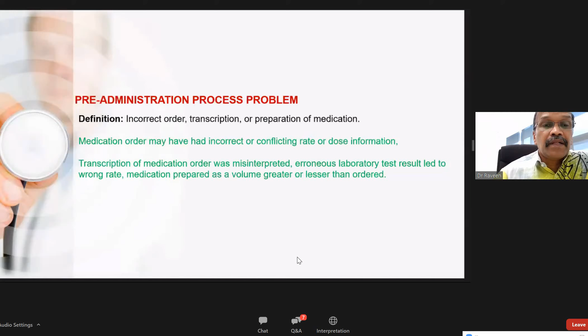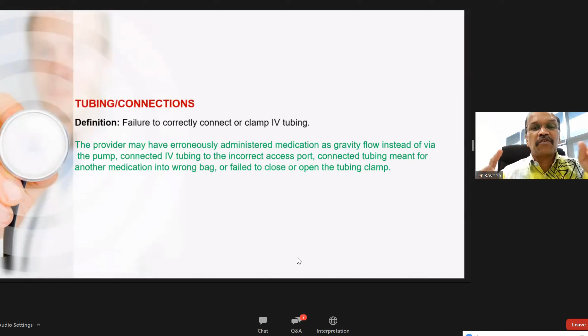Now, failure to correctly connect or clamp the IV tubing. Very often, the most common mistake is you set up everything and you forgot to unclamp the IV tubing. Or you might put up the tubing, everything, but you forgot to program the pump, and instead of running through the machine, it goes directly to the patient. Or the tubing is not connected properly to the IV line, and there is a leak at the site of the connection. The other common thing is when you have IV sets going in, and one has the IV drip and the other one has medication, you switch the two. So they're all going through an infusion pump, and so the wrong medication is now going through at different rates to the patient.